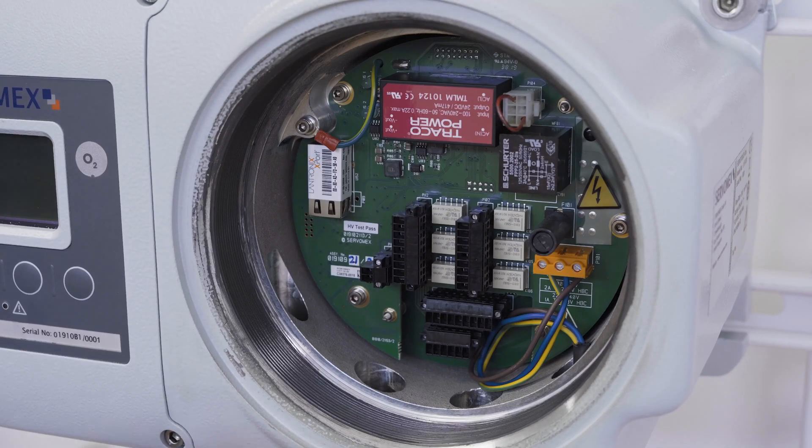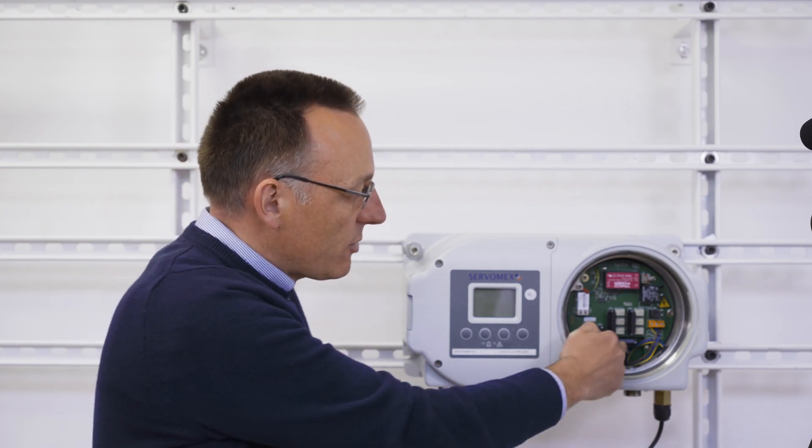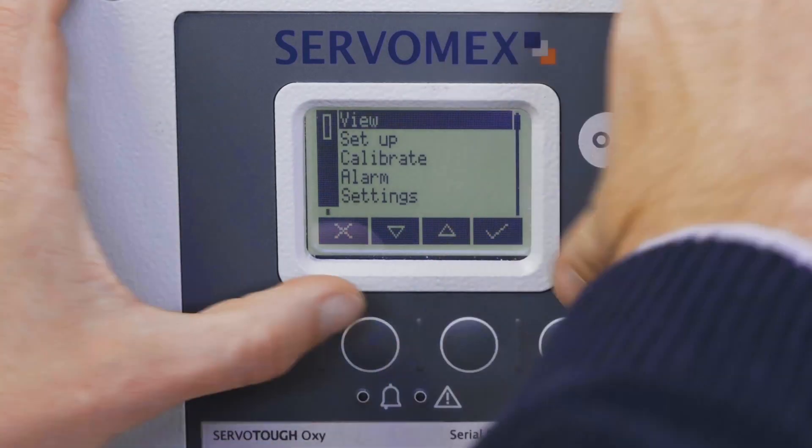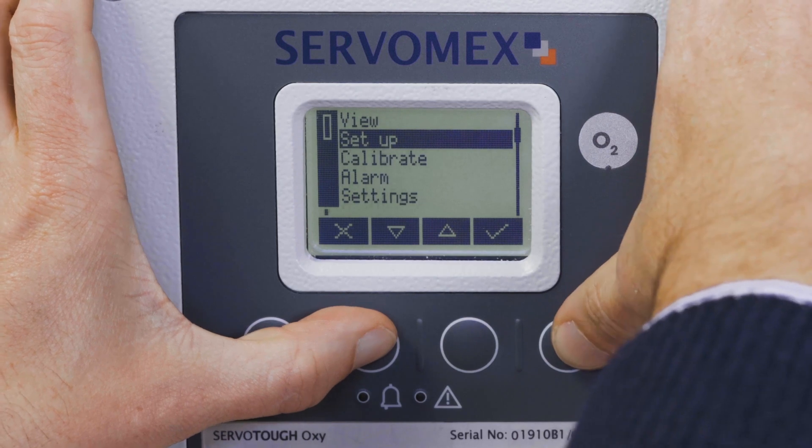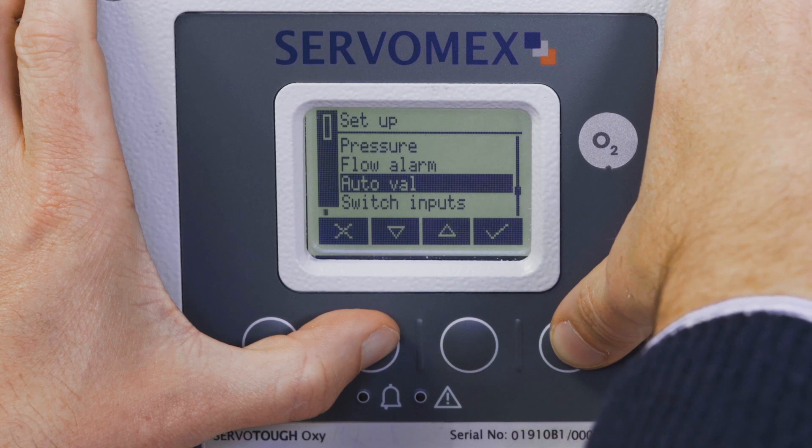An optional auto calibration validation control PCB is available. This adds three additional low voltage relays to control sample low or high calibration gas flows and three digital inputs to control the auto validation calibration sample switching functions that control either automatic or remote calibration modes. The auto calibration or validation cycle can be easily configured from the menu system to suit the specific process requirements.